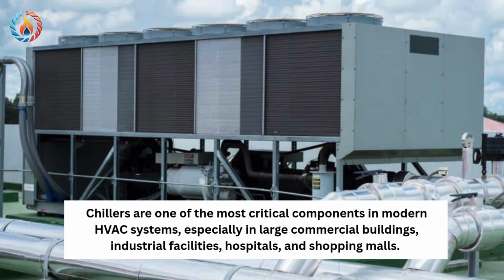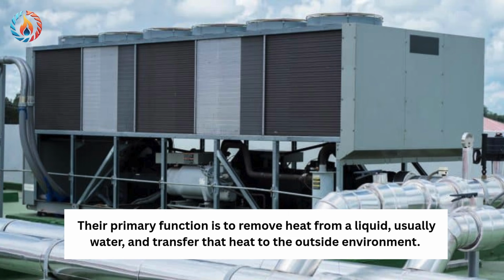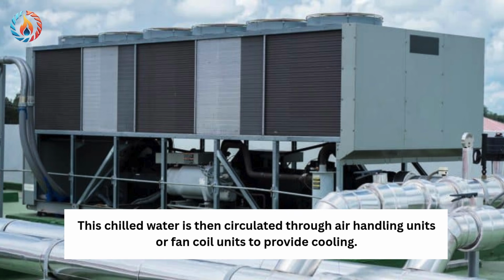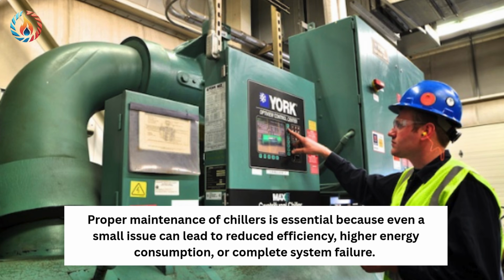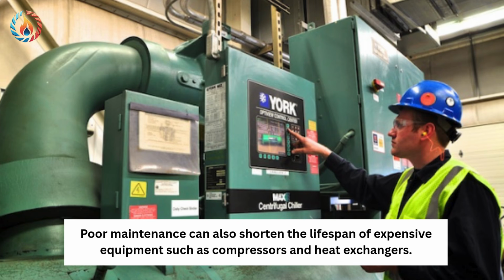Chillers are one of the most critical components in modern HVAC systems, especially in large commercial buildings, industrial facilities, hospitals, and shopping malls. Their primary function is to remove heat from a liquid, usually water, and transfer that heat to the outside environment. This chilled water is then circulated through air handling units or fan coil units to provide cooling. Proper maintenance of chillers is essential because even a small issue can lead to reduced efficiency, higher energy consumption, or complete system failure. Poor maintenance can also shorten the lifespan of expensive equipment such as compressors and heat exchangers.